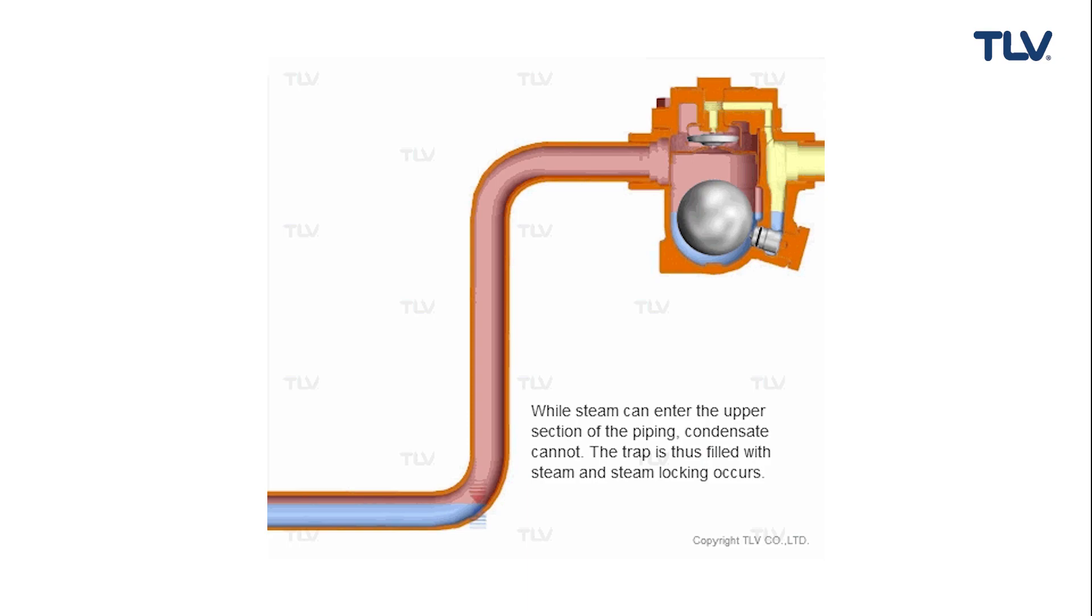Providing extra pressure to forcibly discharge condensate will not resolve the problem, because the valve remains shut by steam.